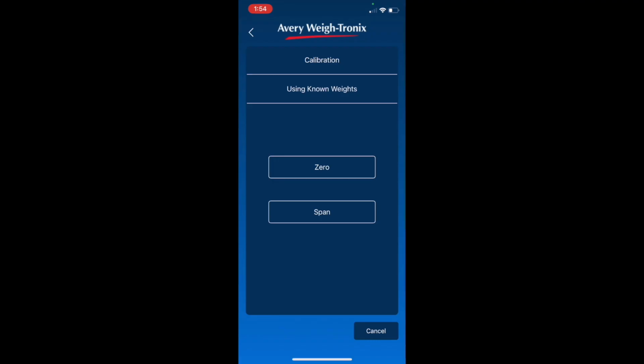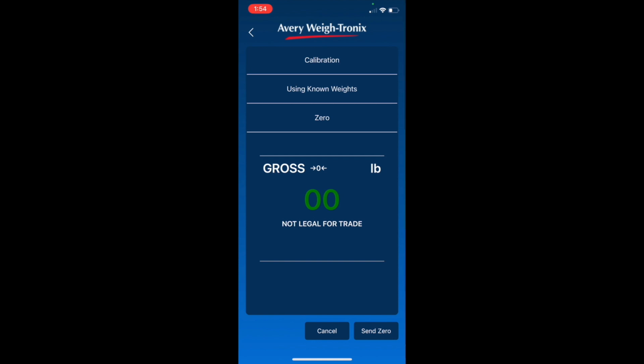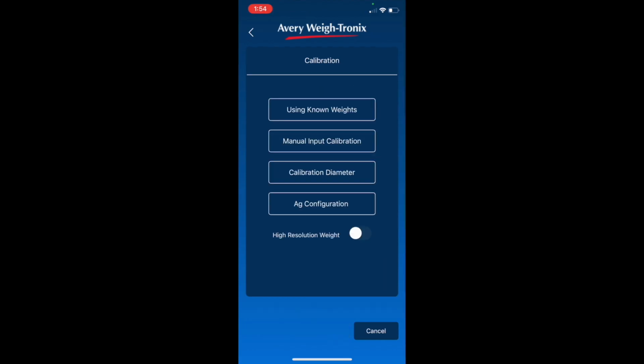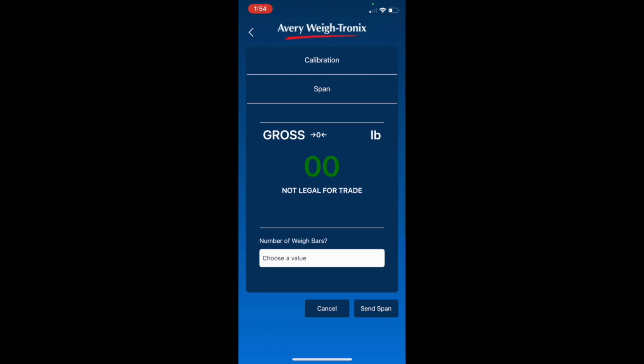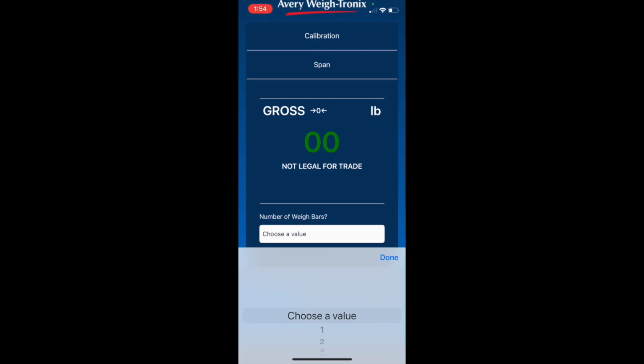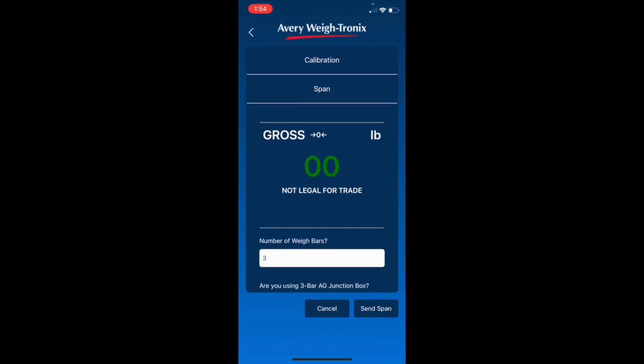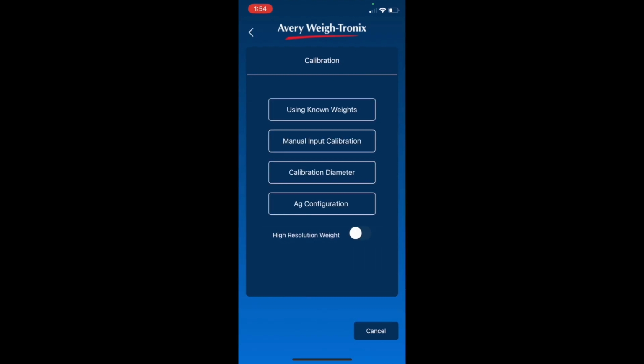Using a known weight, you can zero the display and then put a known weight on the display. Let's go to manual input calibration. Choose a value to select the number of weigh bars. And then you can send the span. We'll back out of this.